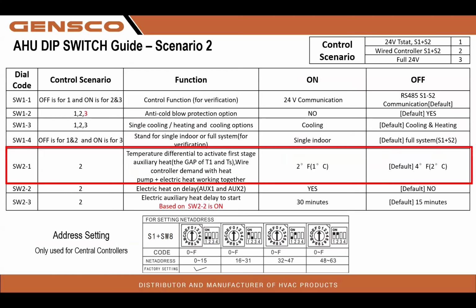SW2-1, control scenario 2, which we are talking about right now, fully communicating. Temperature differential to activate first stage auxiliary heat. The gap of T1 and TS wire controlled demand, with heat pump plus electric heat working together. 2 degrees is dip switch SW2-1 in the on position. Default, right out of the gate, dip switch in the off position is a 4-degree deadband.